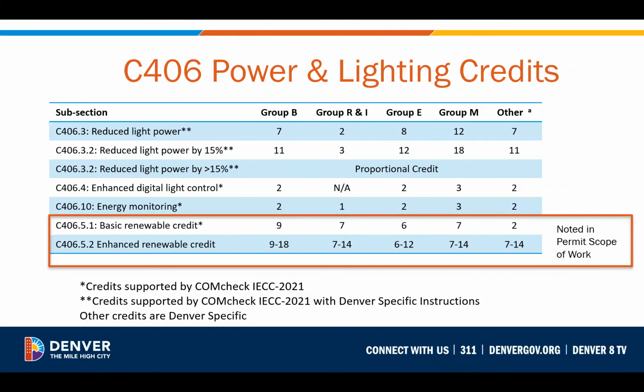Enhanced digital lighting control is a credit available to all occupancy groups except residential multifamily buildings. This credit requires advanced capabilities, including continuous dimming and load shedding capabilities, as well as individually addressable luminaires. This is also known as luminaire level lighting controls, or LLLC. If you haven't heard of this system, I would recommend looking further into them. These systems have great savings potential by enabling control of individual or small groups of luminaires to dim or shut off in response to occupancy or daylight levels or any other factors.